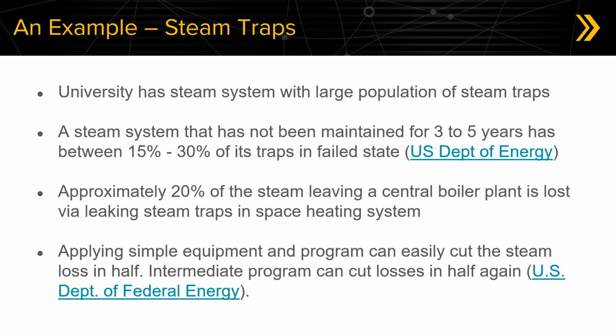A previous customer, a large university here in the US, has a steam system with a large population of steam traps. Looking at basic US Department of Energy statistics, any steam system that hasn't been maintained for 3 to 5 years has about 15 to 30% of its traps in a failed state. They're just prone to failure, and over time approximately 20% of the steam leaving that boiler plant is lost via leaking steam traps in a space heating system.